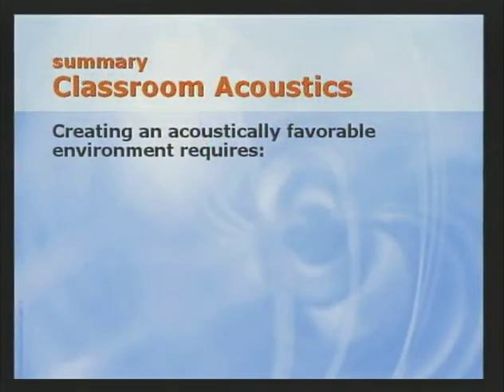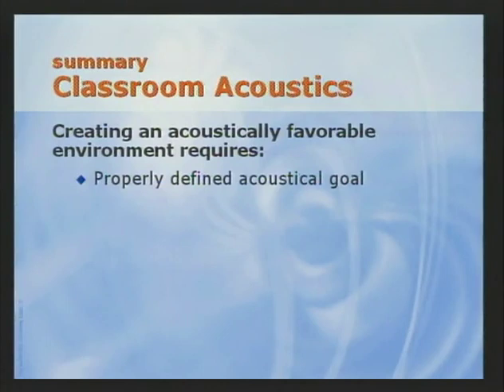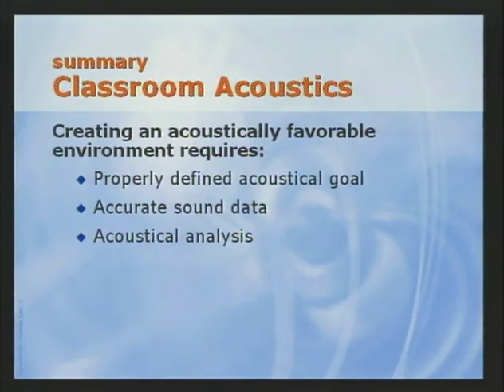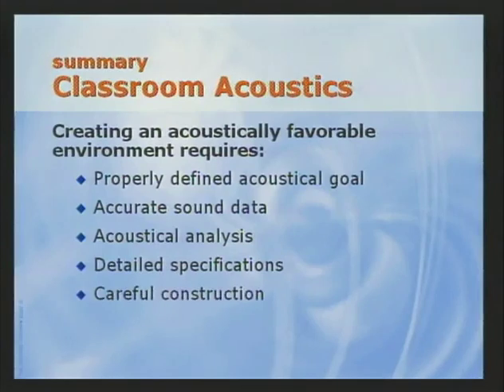In addition to the path attenuation options that I've mentioned, central systems typically offer flexibility in source attenuation options. In some cases, it's possible to change the fan type, add a plenum, or pick a different unit configuration that will significantly reduce the sound produced by the unit. There's lots of material to cover on classroom acoustics, and we've just skimmed the surface. The important point to remember is that proper acoustics can make classrooms much more effective learning environments. Creating a high-performance school in this context is a matter of designing to attain the acoustical target. The ingredients for acoustical success are the same as the ingredients for acoustical success on any project. They are a properly defined acoustical goal, accurate sound data, acoustical analysis, detailed specifications, and careful construction.